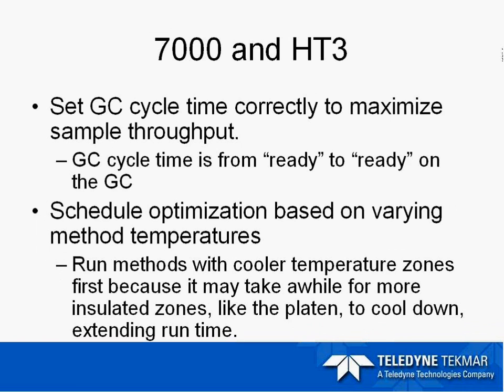Moving on to topics common to both the 7000 and the HT3: make sure the GC cycle time is set correctly to maximize sample throughput. We define the GC cycle time as ready to ready on the GC. If you have a 16-minute GC run time, give it a couple extra minutes to get back to the ready state for the next sample. Also optimize your schedule based on varying method parameters — if running multiple methods, run the methods with cooler temperature zones first because it may take a while for the platen to cool down, which could extend your sample run time.